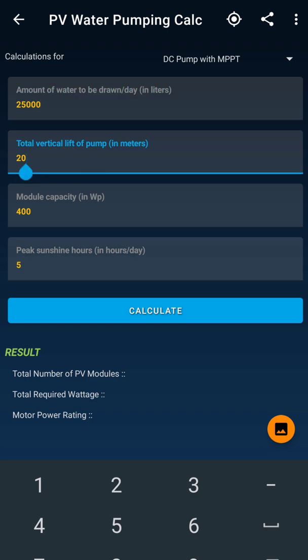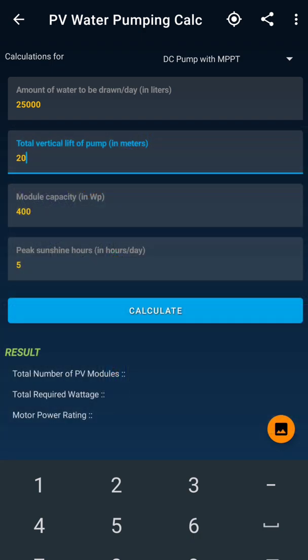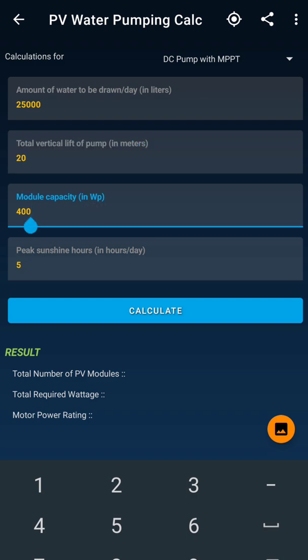The second thing the app is asking is the total vertical lift of the pump. If you are going to use a submersible pump, there will be a certain depth of the borewell, and that is what it is asking. I know one place where the depth of the borewell was 20 meters, so I have selected that. This detail will depend on how deep your borewell is.